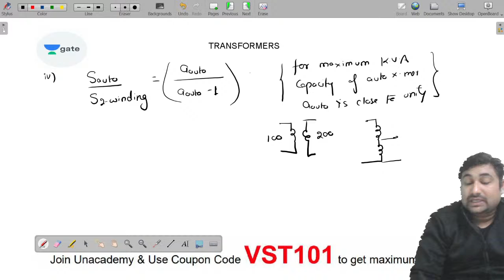It means, sir, let us suppose we have a two winding transformer, say of 100 by 200 volt, and we have to connect it as an auto transformer. So we must connect the auto transformer for maximum kVA capacity in such a fashion that A auto should be close to unity. If we have the windings, say A, B, C, D, this is a two winding transformer. We have to connect it as an auto transformer, so we must connect it in additive polarity with A auto close to unity. So for that, you must select CD here and AB here.